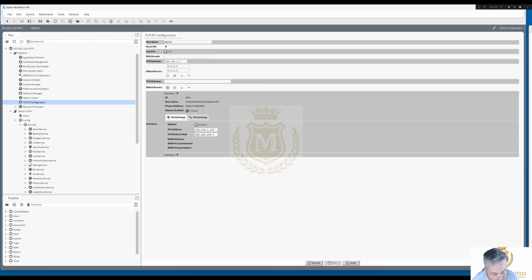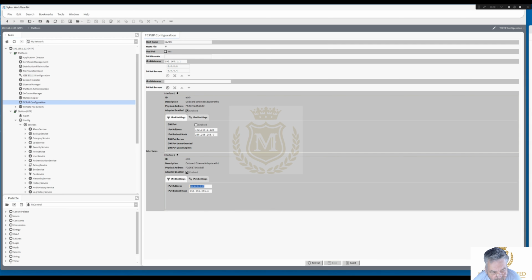If that's connected to the system, talking to fan coils or whatever via IP, I can always get into the controller by the second port and set my laptop to say 10.0.0.126, and then I can go in using the workbench on 10.0.0.125, and I'm not disturbing any of the network when I'm on site. So that's the reason why I use that second one.